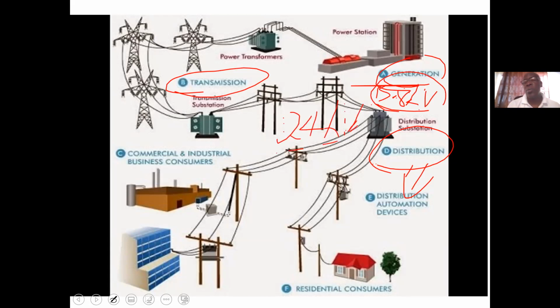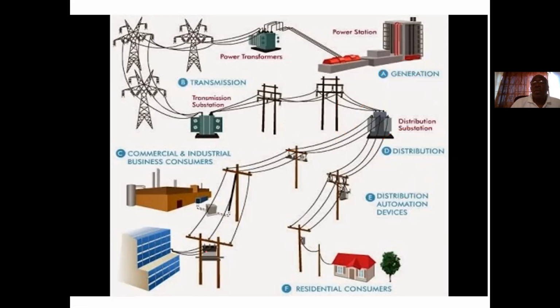Speaking specifically about Jamaica, for our purposes we generate at an average of 13.8 kilovolts. That 13.8 is then transformed by our power transformer to transmission level voltages, or in some jurisdictions, sub-transmission. So we take it from 13.8 and increase it, in Jamaica, up to 69 kilovolts, and we use that for transmission.